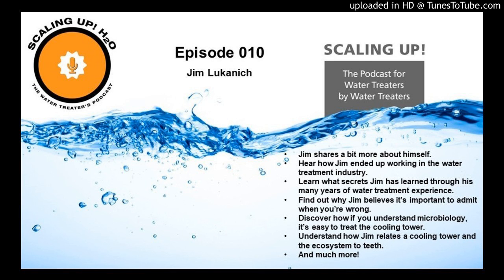Now, let me qualify that a little bit. It's important to do that, especially in systems that may be highly contaminated with solids, because your polymer will tend to adsorb out. And when active groups on the polymer adsorb out, they're no longer active, and so you may lose activity. It's important to do in long holding time systems where the volume to load ratios are very, very high, and your half-life of your system is very long, because your polymer is going to adsorb out, and make it down to a level below at which it's still going to be functional.